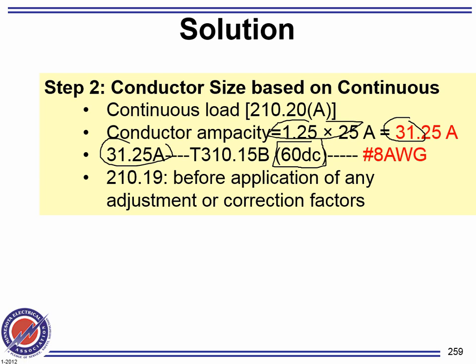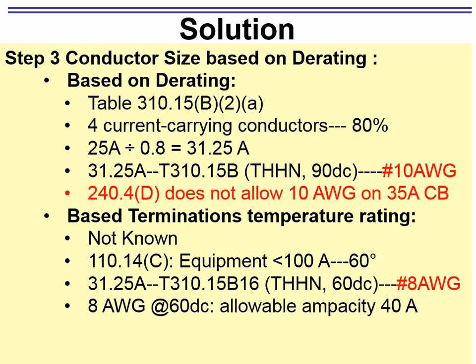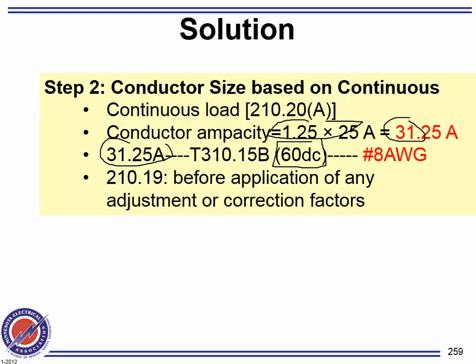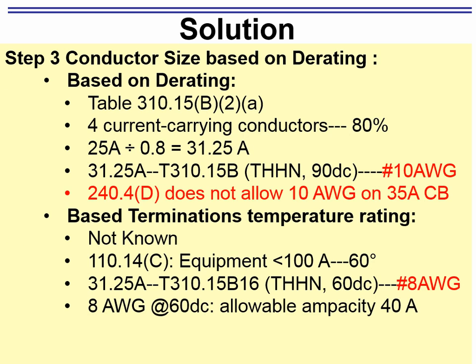So my first solution, guys, would be based on continuous load. My conductor would be, this would be 35, and the conductor will be number 8. Okay, now stop there, put it aside, and let's go size the conductor based on temperature, or bundling.